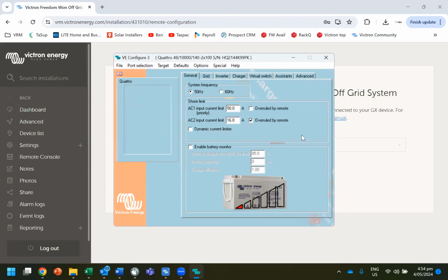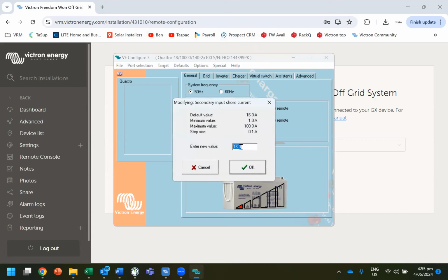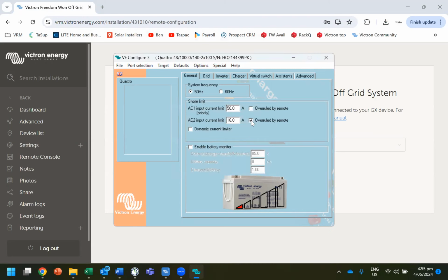There it is. So we can see that it's been configured for 16 amps on the AC2 input. So I'm going to assume that the generator can handle 16 amps. Now it's got overruled by remote. That means that if you're not sure about what the generator can handle, if you click overruled by remote, then you can change the setting on the fly through the touch screen or the Color Control screen on site. So that's great. If the generator's starting to struggle, you can just ramp back the current a little bit.